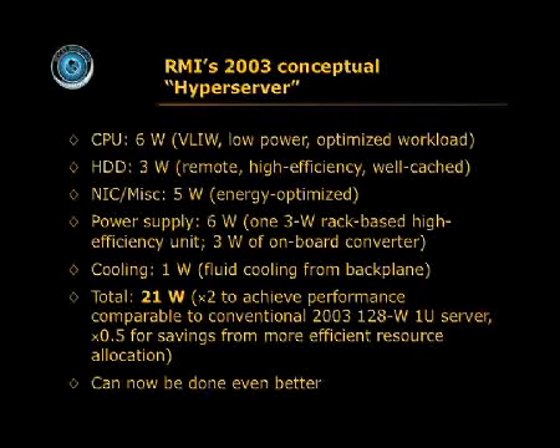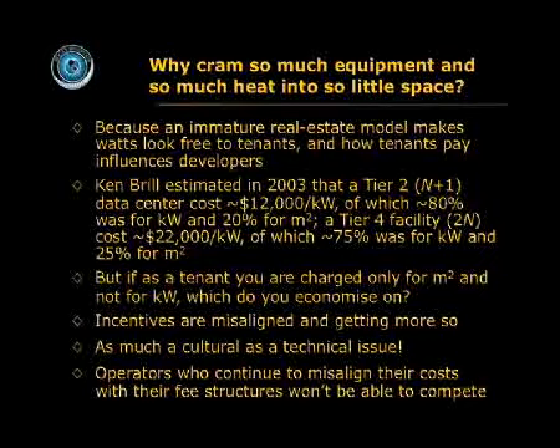Now we can do considerably better than that. And you might ask yourself, why do we have so many problems in data centers from cramming so much equipment and so much heat release into so little space? Well, because we really adopted an immature real estate model that made the watts look free to the tenants. And of course, Ken Brill estimated even 5 years ago that a Tier 2 data center would cost you about $12,000 a kilowatt, but 4/5 of the capex was for the kilowatts, only 1/5 was for the space, the things that occupied space. In a Tier 4 facility with full 2N redundancy, $22,000 a kilowatt, 3/4 of the cost driven by the watts, not the space.